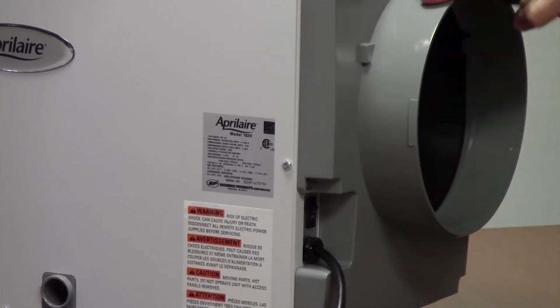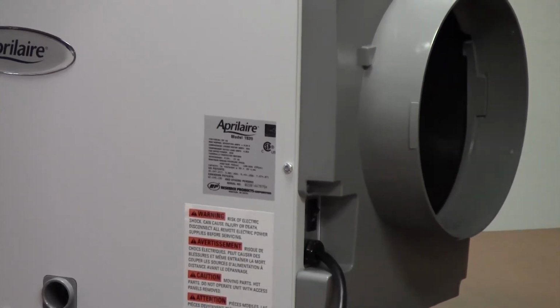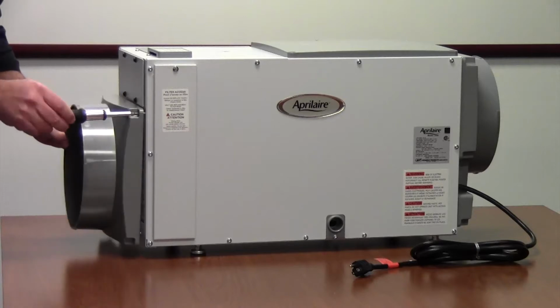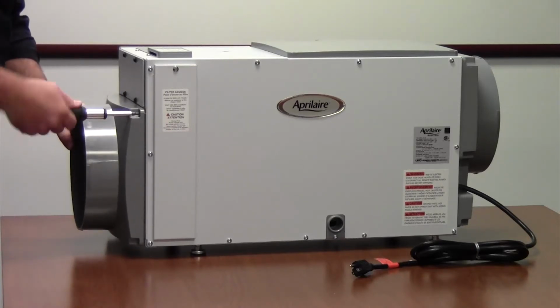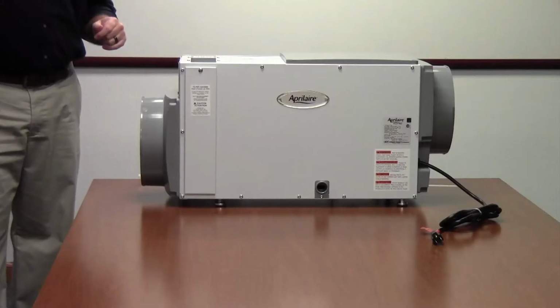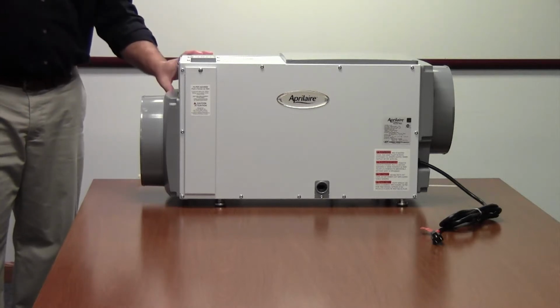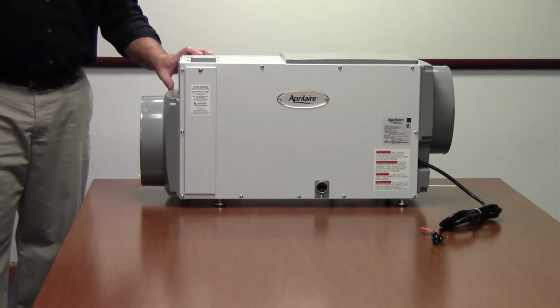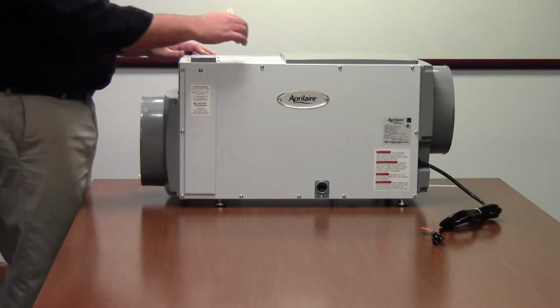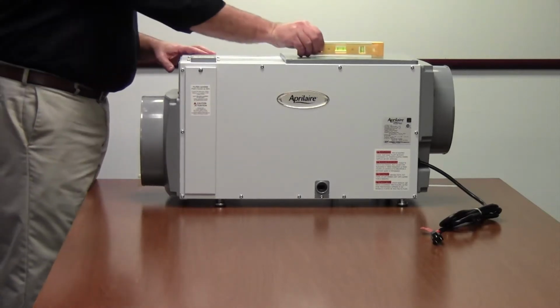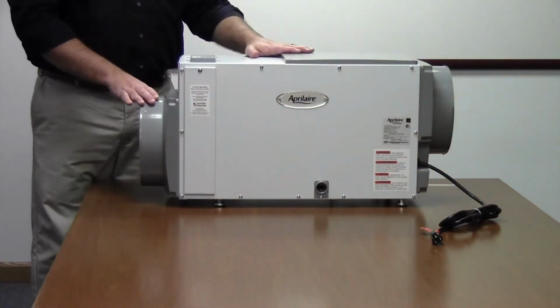Okay, there are 5 screws on this collar, and then on the inlet collar there are 4 screws. Once we get the duct collars attached to the unit and we've decided where to put it, we're going to make sure that we level it, make sure it's level side to side and front to back. Now we're just going to talk about ducting a little bit.